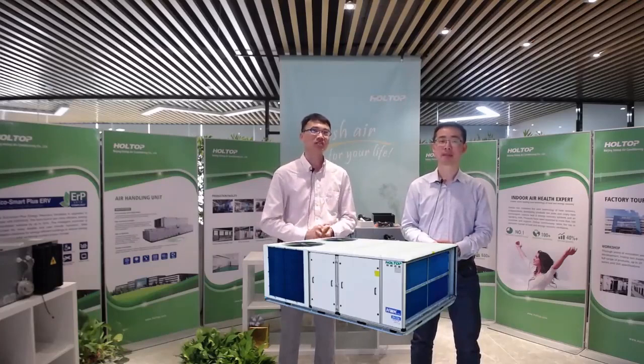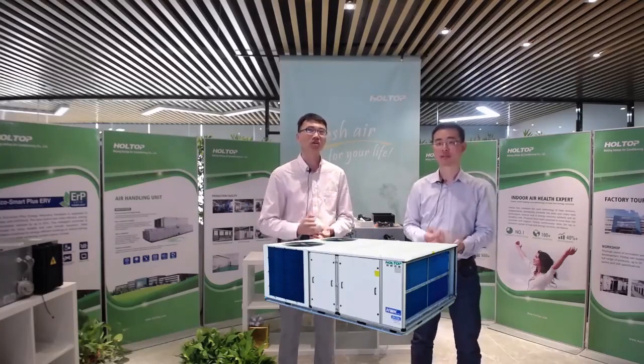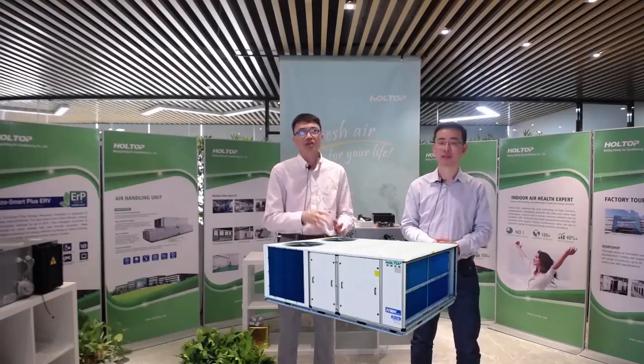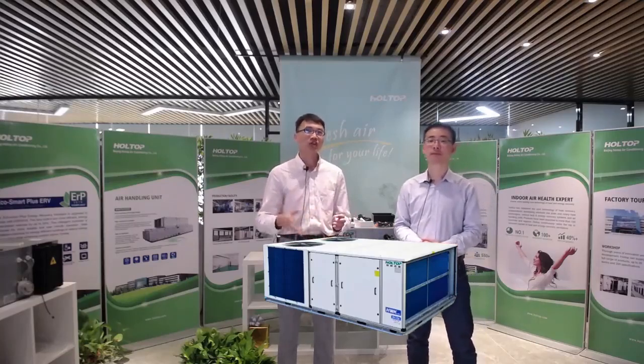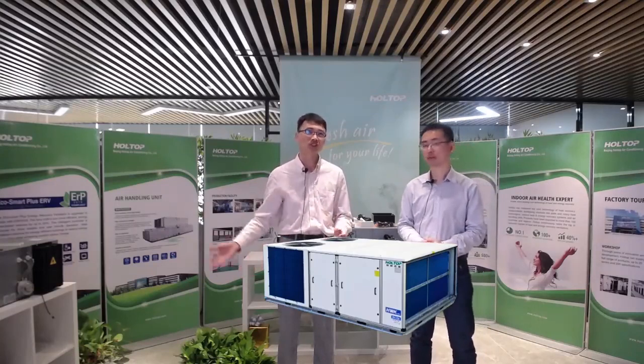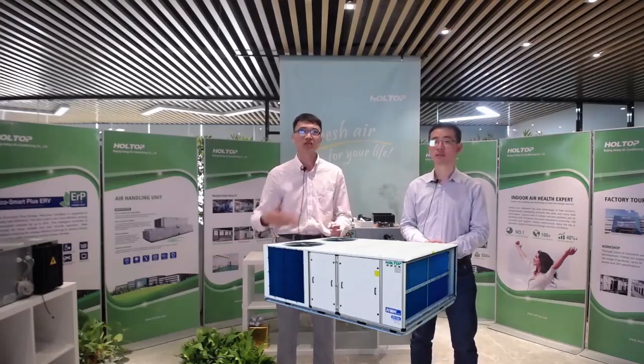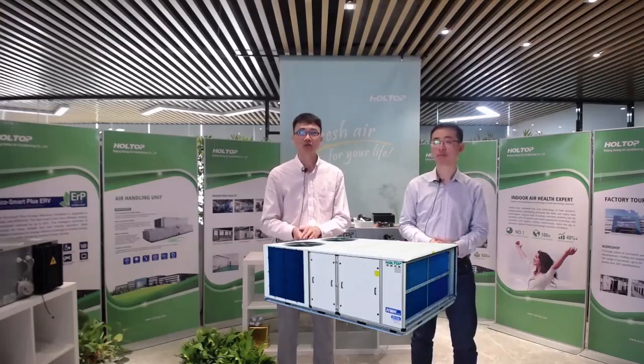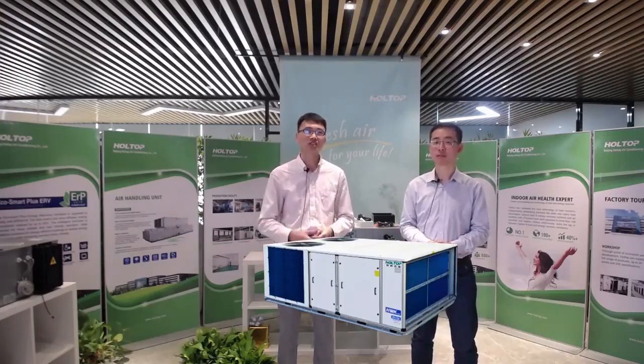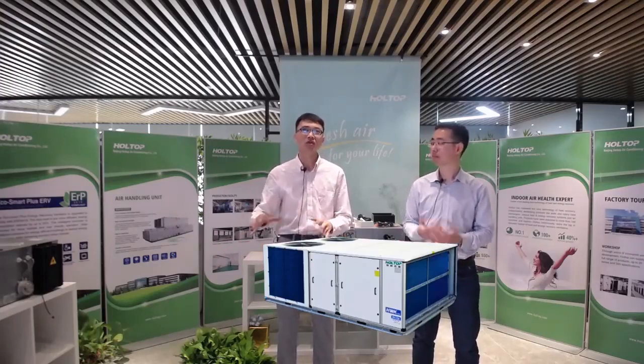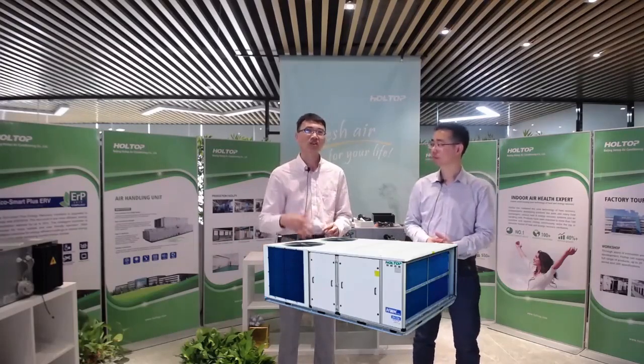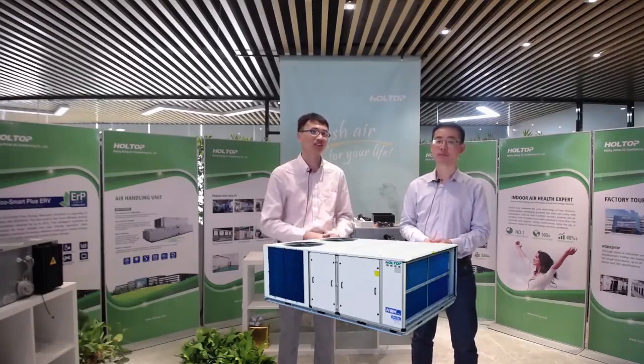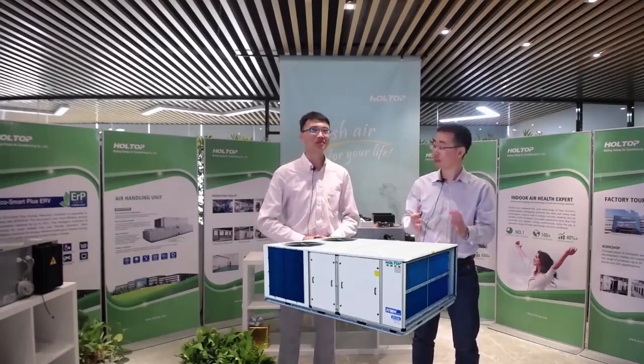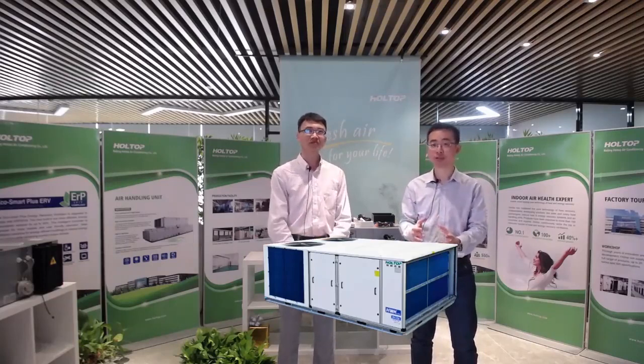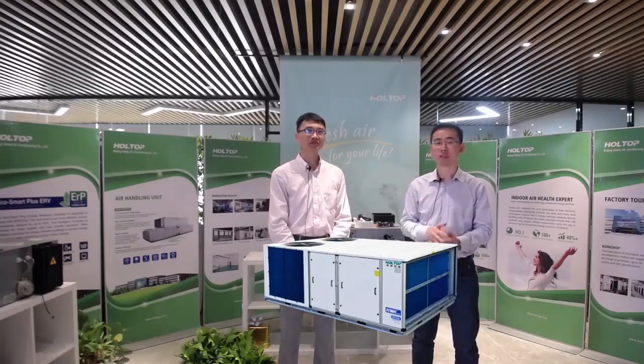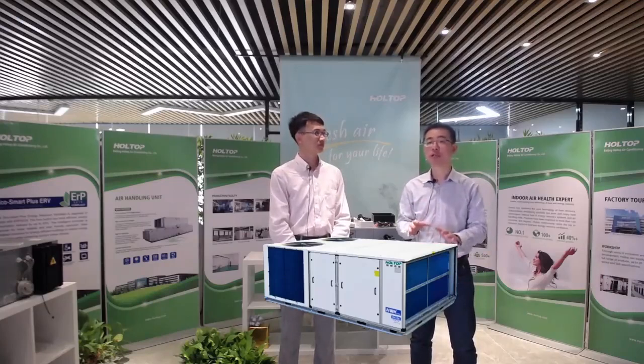The first one is the simplified system and lower investment. Rooftop package unit asks for neither a chilled water system nor a cooling water system, which can save the cost of the circulation pump, cooling tower, and some other relevant equipment in this system. So it cuts down the total investment and maintenance cost of the HVAC system to a great extent. It is a compact design, with easy and flexible installation and a low footprint. Users' requirements on installation are fully considered.